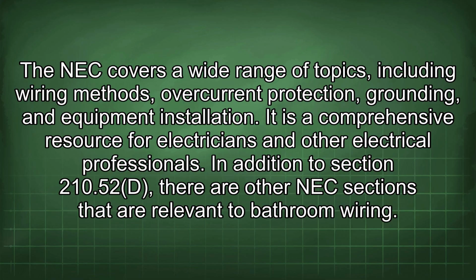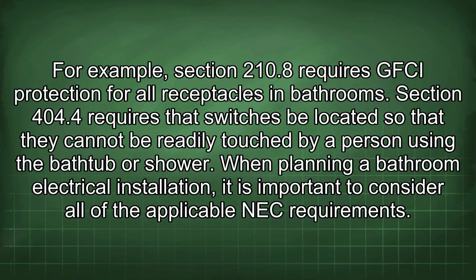In addition to Section 210.52(D), there are other NEC sections that are relevant to bathroom wiring. For example, Section 210.8 requires GFCI protection for all receptacles in bathrooms. Section 404.4 requires that switches be located so that they cannot be readily touched by a person using the bathtub or shower. When planning a bathroom electrical installation, it is important to consider all of the applicable NEC requirements.